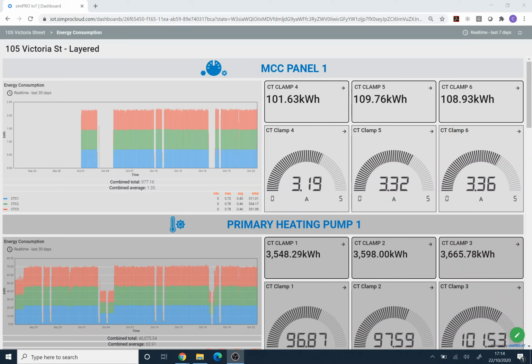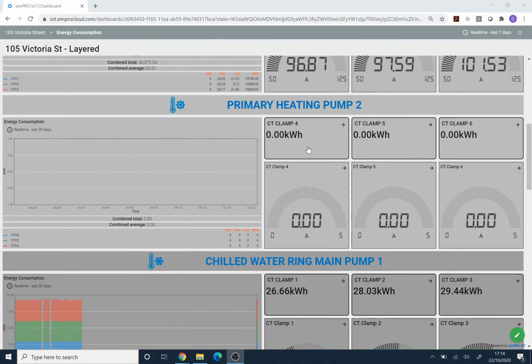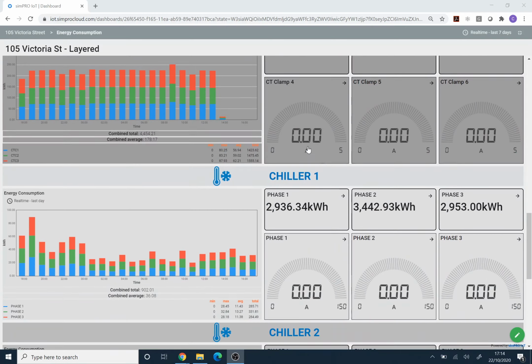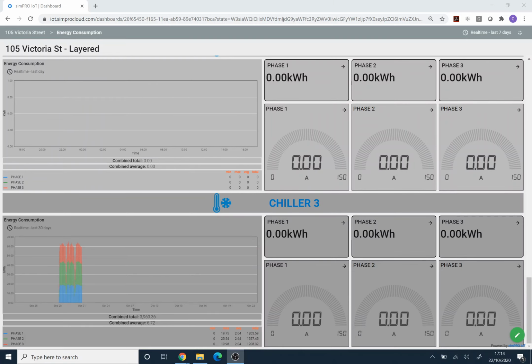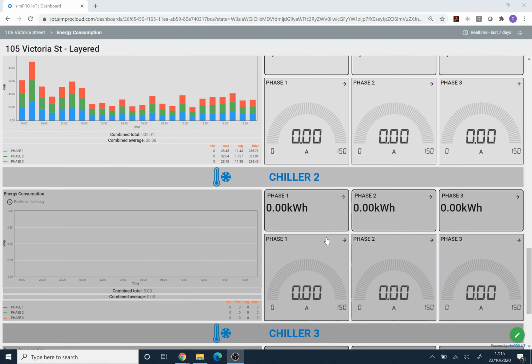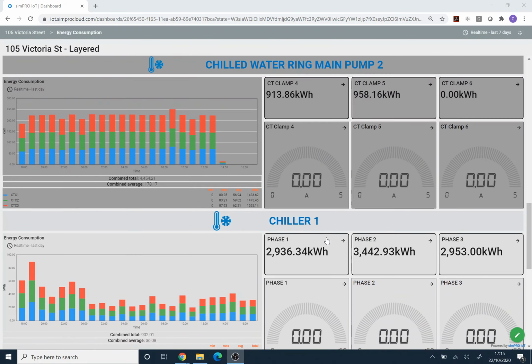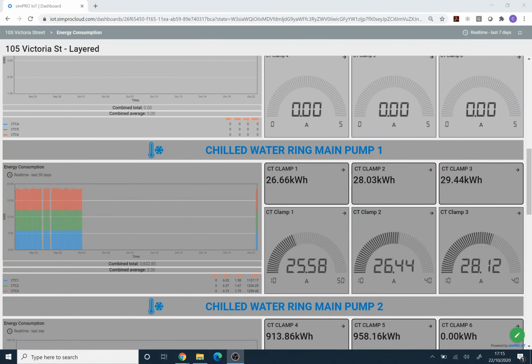To complement these core measures, we have also introduced our power monitoring nodes for key assets, including the MCC panel, heating pumps, chilled water main pumps, and the chillers. This data gives a clear indication of equipment status and operating performance. The following information is available on this dashboard. For each phase, the total kilowatt hours based on the dashboard time period set, the current last recorded amperage value for each phase, and then a historical time series chart. These charts are set up for individual time periods on this dashboard, but these can easily be changed to a global dashboard level setting if required.